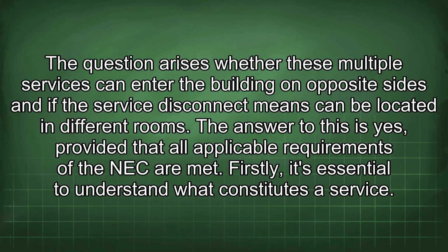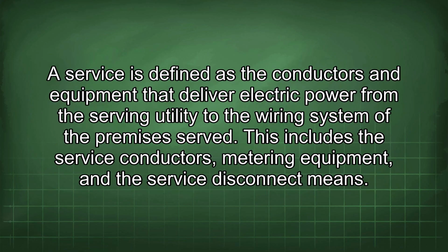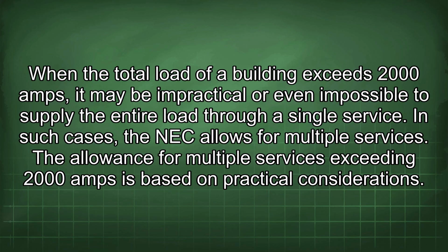Firstly, it's essential to understand what constitutes a service. A service is defined as the conductors and equipment that deliver electric power from the serving utility to the wiring system of the premises served. This includes the service conductors, metering equipment, and the service disconnect means. When the total load of a building exceeds 2000 amps, it may be impractical or even impossible to supply the entire load through a single service. In such cases, the NEC allows for multiple services.